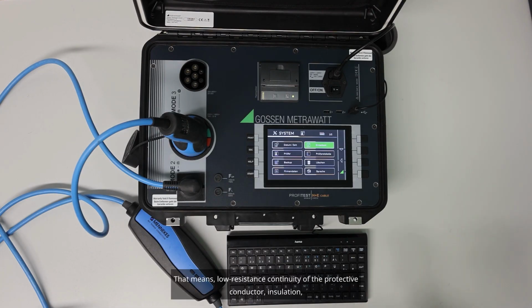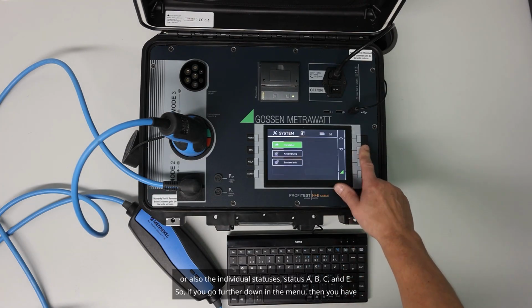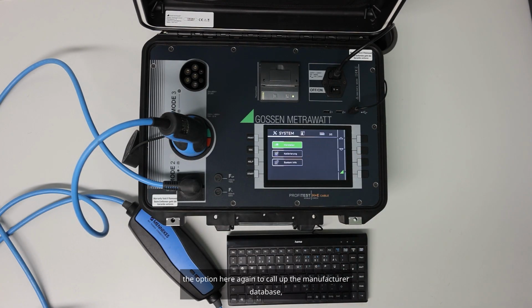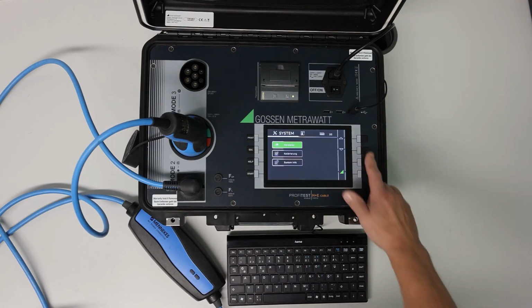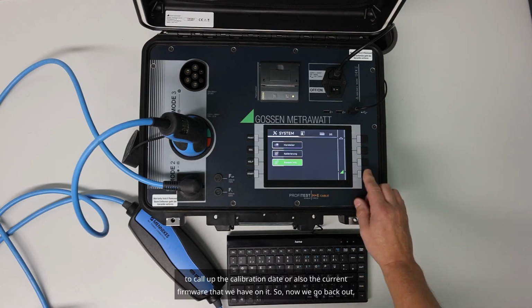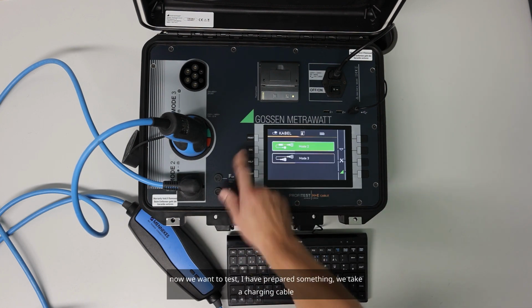That means low resistance continuity of the protective conductor, insulation, RCD test, 6 mA test, so checking the sensors, or also the individual statuses, status A, B, C, and E. So if you go further down in the menu, then you have the option here again to call up the manufacturer database, to call up the calibration date, or also the current firmware that we have on it. So now we go back out, now we want to test.